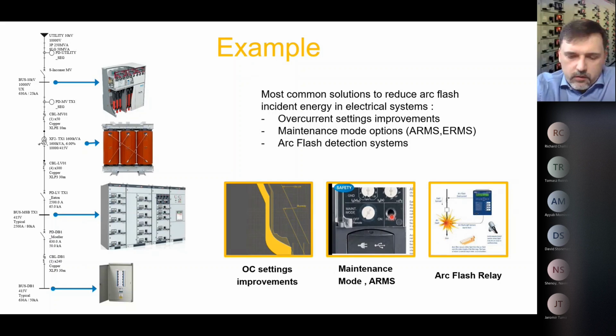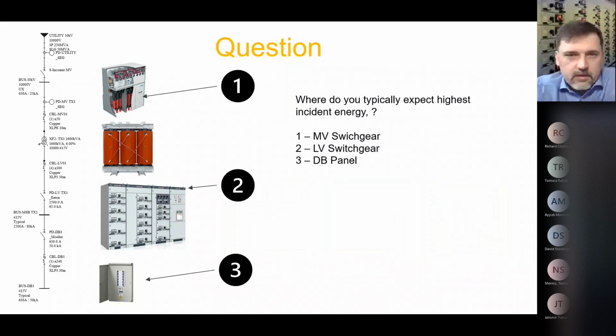And in this one, I think it was a data center, we had this. So, just again, a question, but you will not answer it. I'm not asking you. Where would you typically expect the highest energy: in medium voltage, low voltage, or the panel board? I can answer that it will be on the low voltage panel, especially on the incoming side of the low voltage panel. So the low voltage side of the transformer will probably be the worst one as well. But this is a rule of thumb, it doesn't have to be this way.